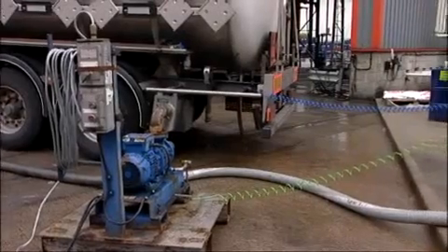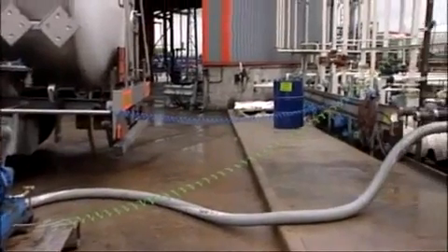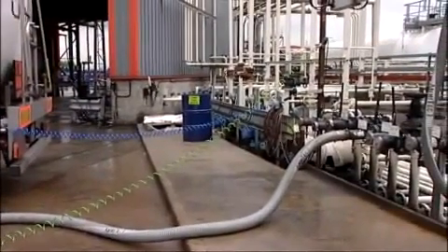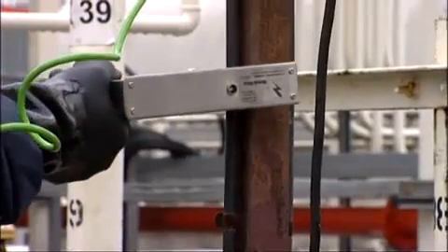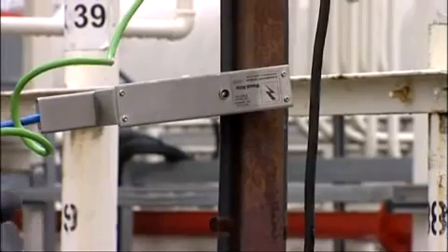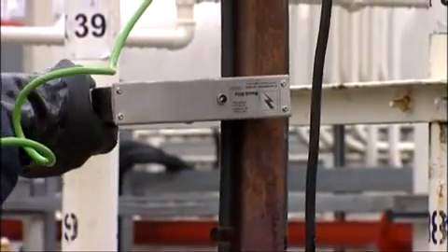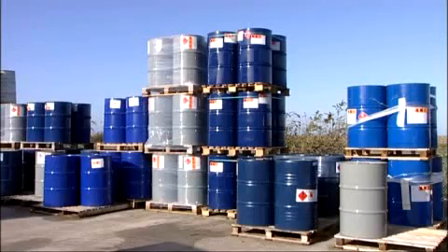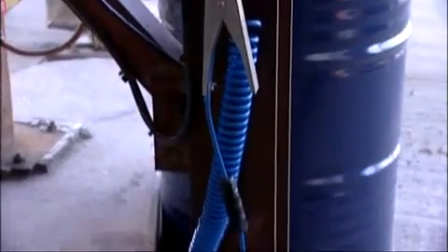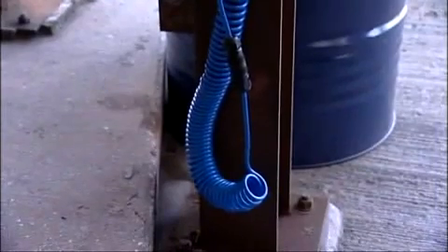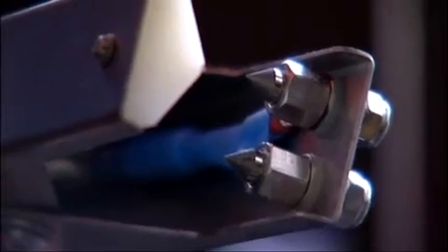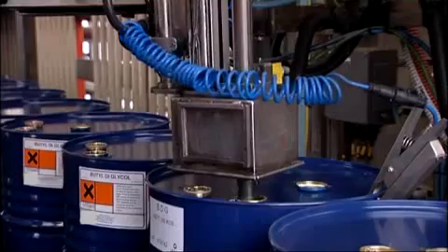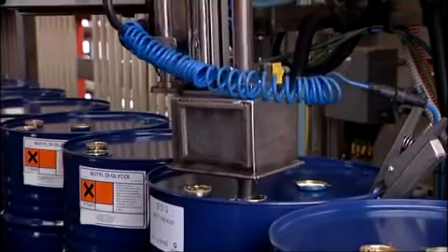Portable equipment must be earthed back to the process equipment or common earthing system, using the appropriate flexible cables and clamp. The clamp must make contact with metal surfaces through paint, rust and surface contaminants. Drums and cans must be earthed back to the loading system via earth leads and a special earthing clamp that penetrates the paint coating. Preferably, the earthing clamp is in a separate location to the source of the flammable atmosphere.